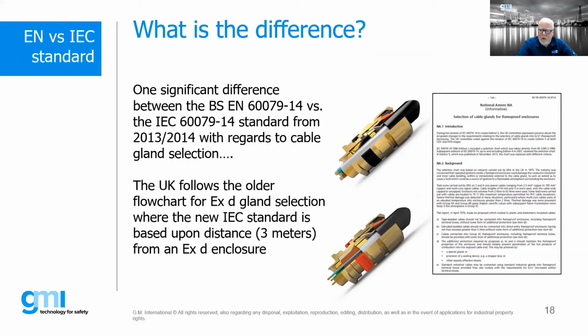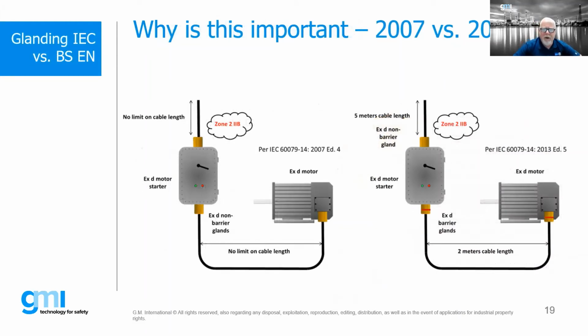So what the UK did in particular, they put in a national annex to their version of BS EN 60079-14. And basically this national annex goes against what is referenced in the EN standard, saying, look, if you're going to do something in the UK, you need to do something a little bit different.